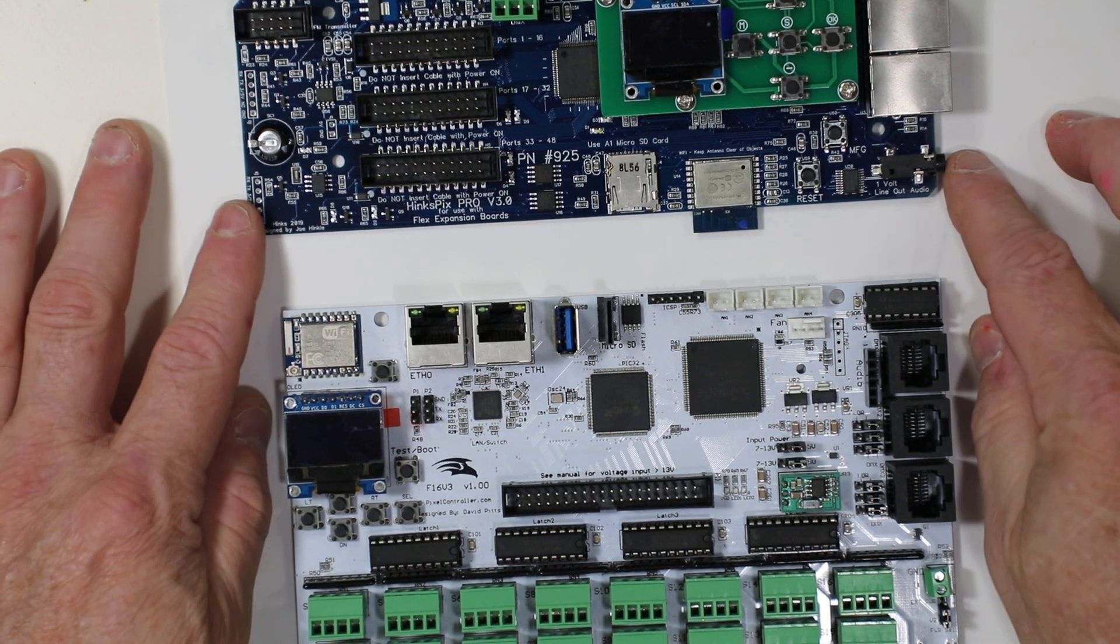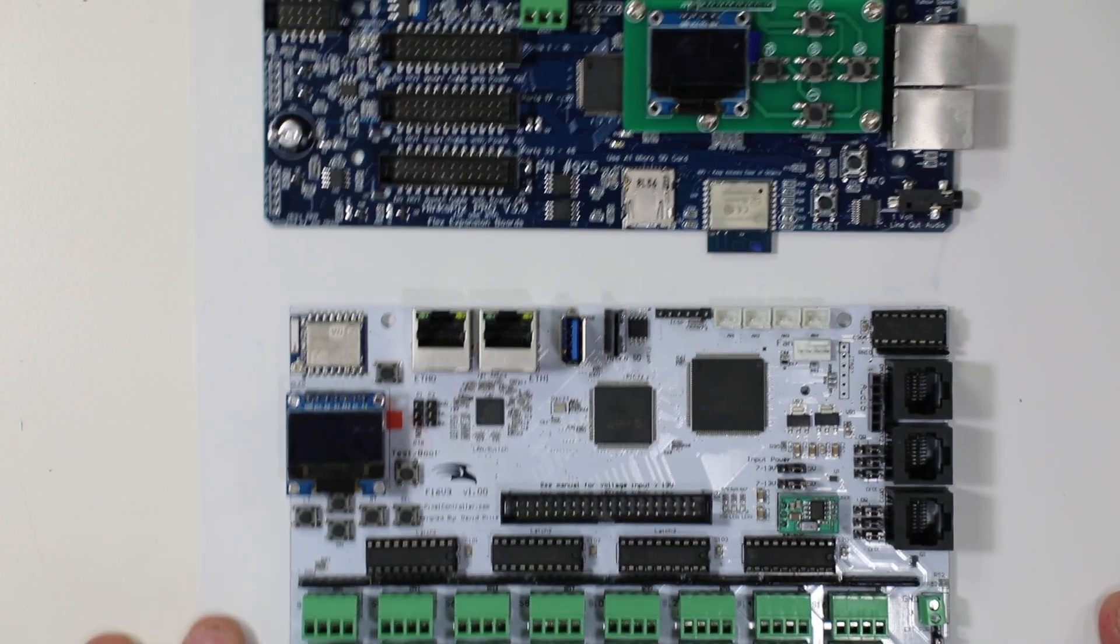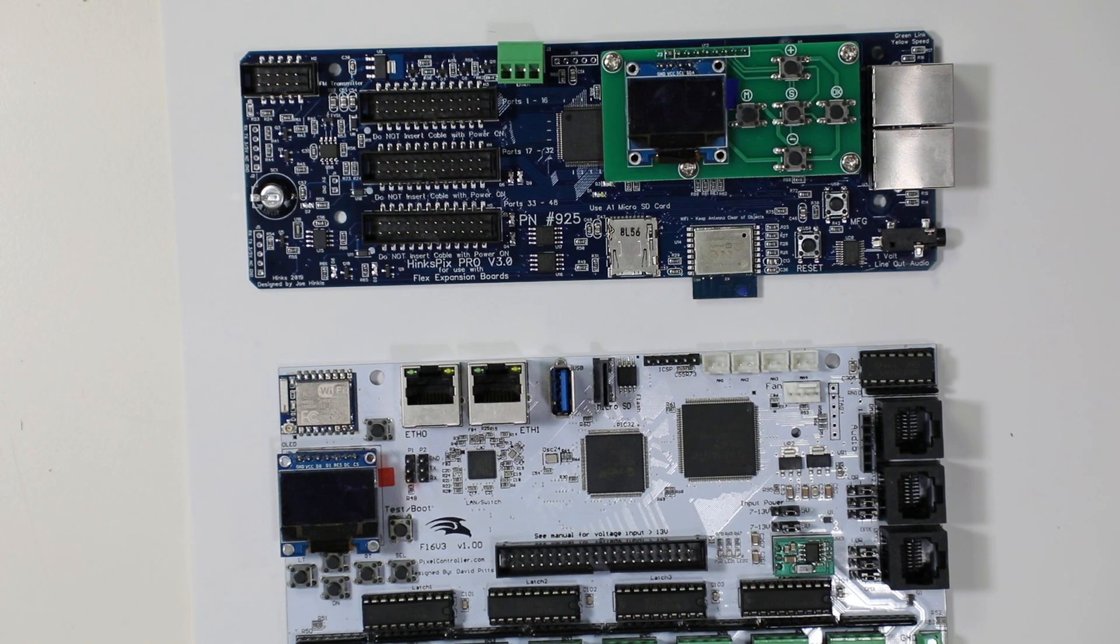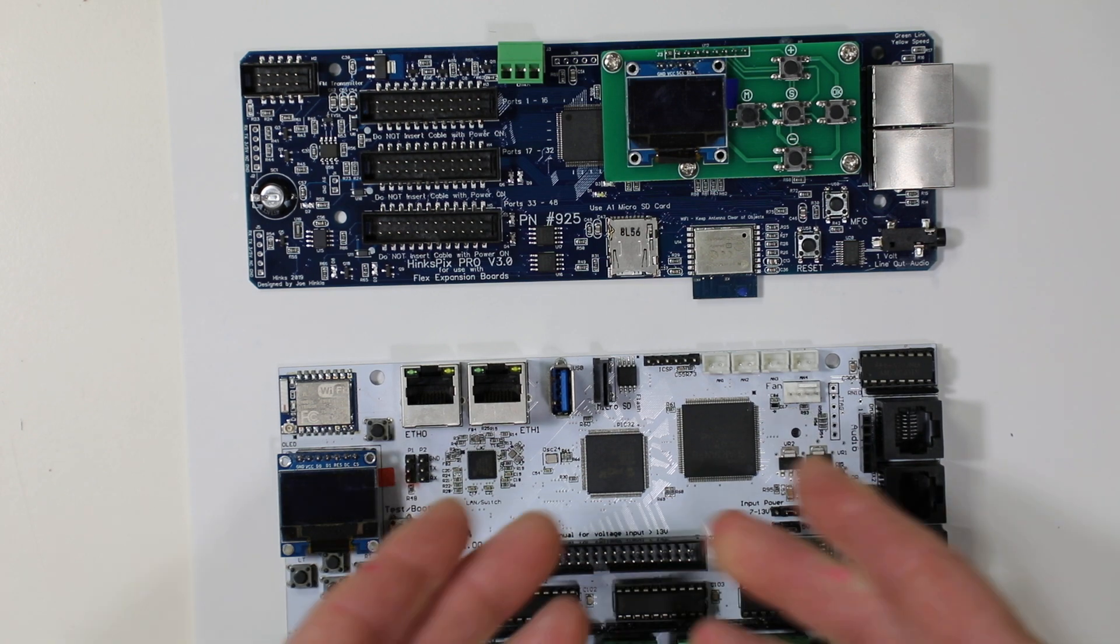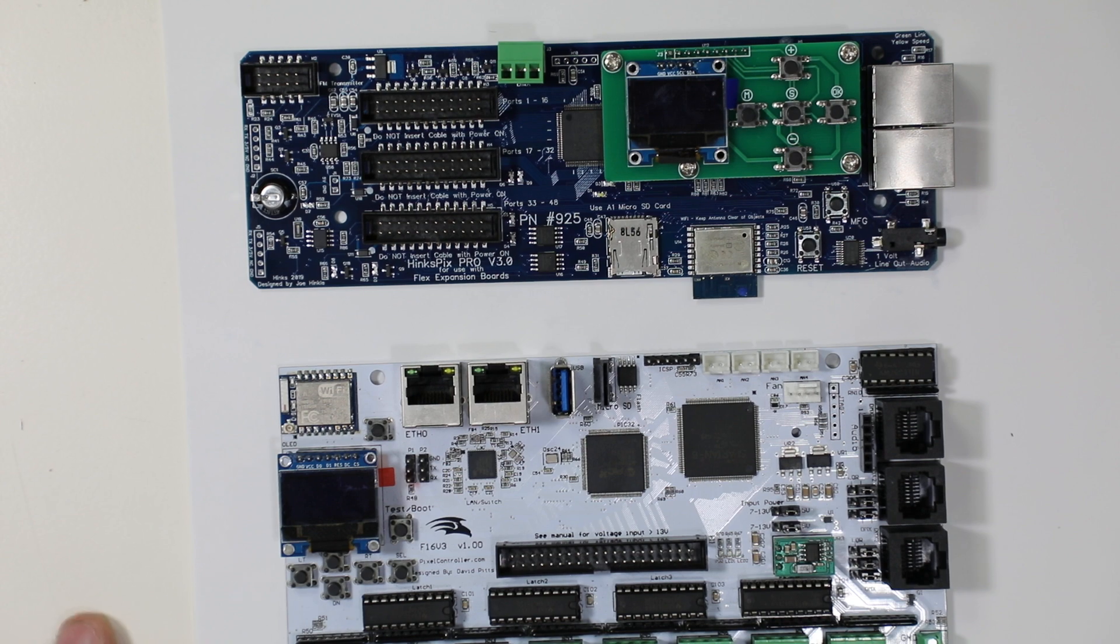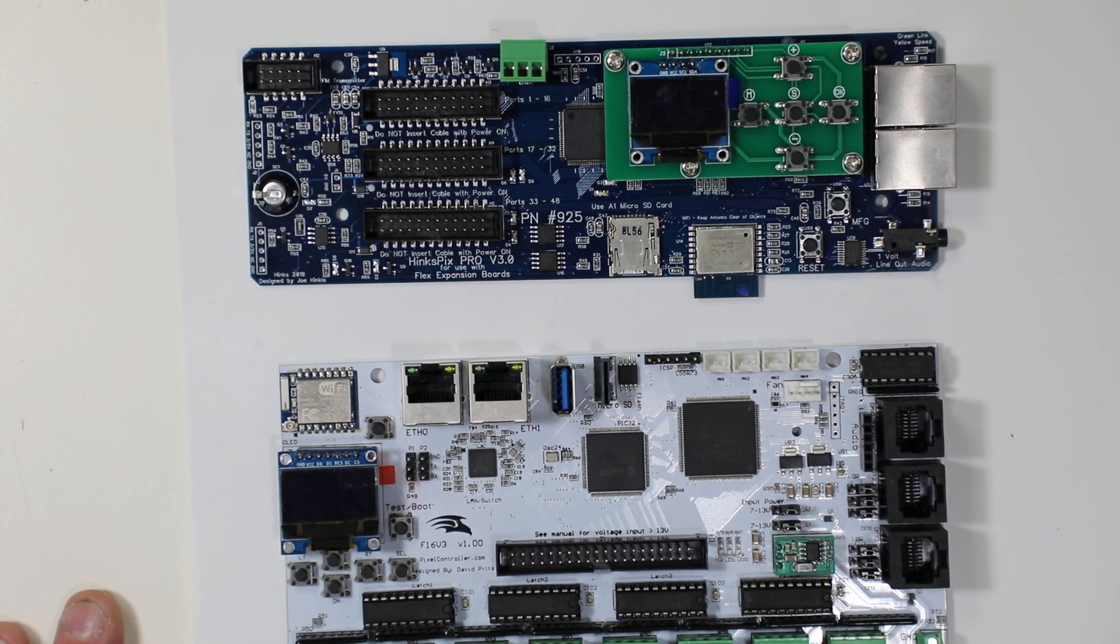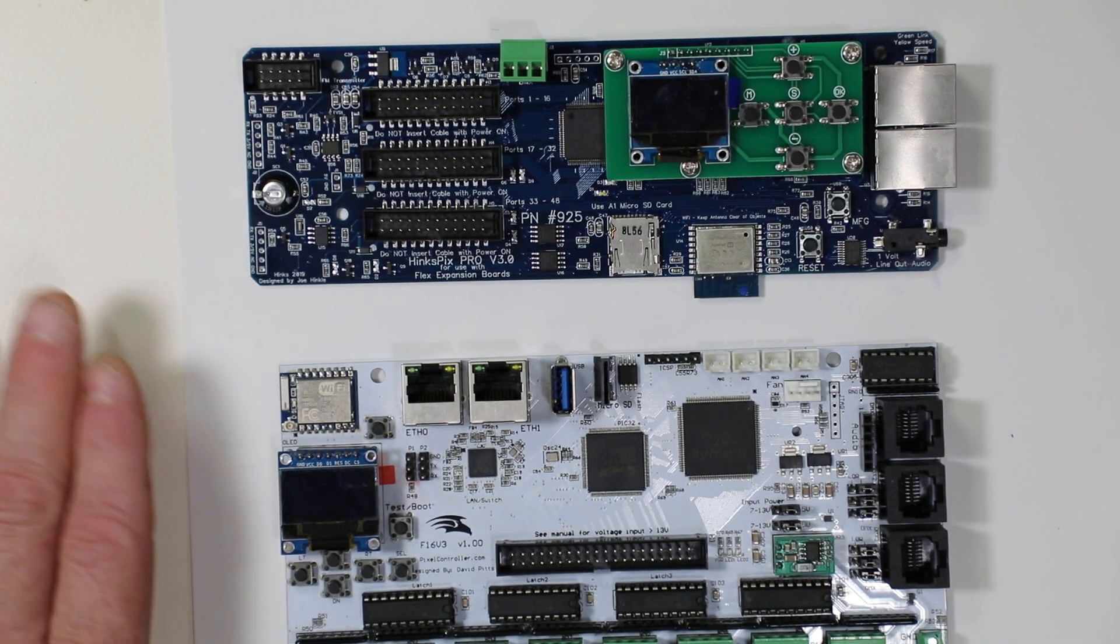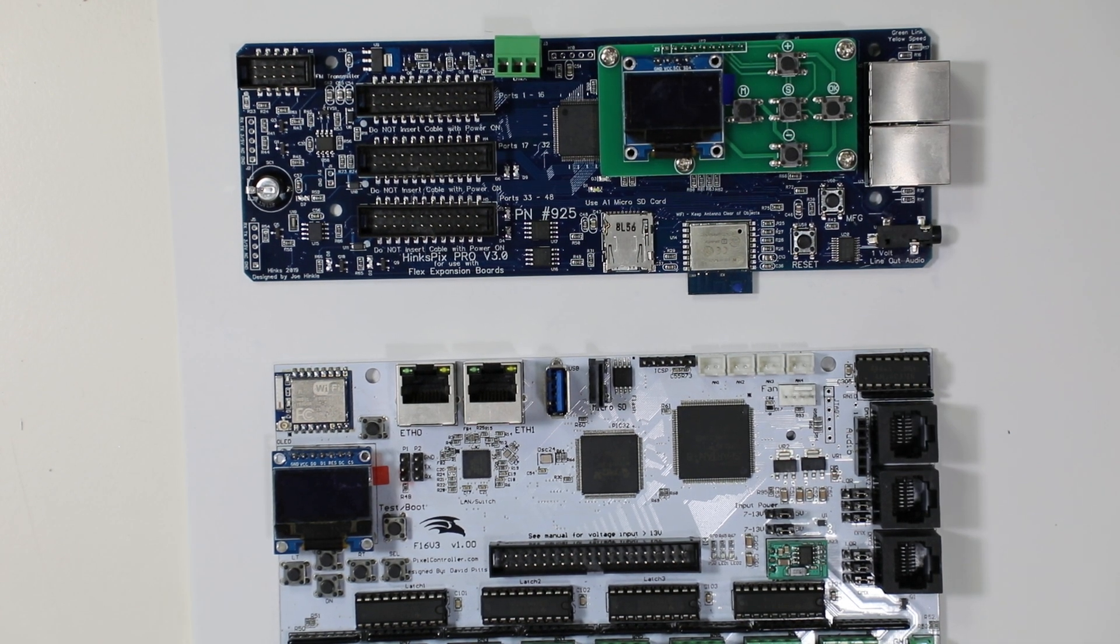and also the network congestion and other factors that are well beyond this controller, such as exclusivity to a network. So if you have a shared network with a whole bunch of other data on it, those controllers have to sync or have to share that bandwidth along with the other devices on the network. So if you're doing wireless, you need to do your homework, plan everything out, test, test, test, and then use wireless. If you're not sure, use the cable. You'll be much happier.